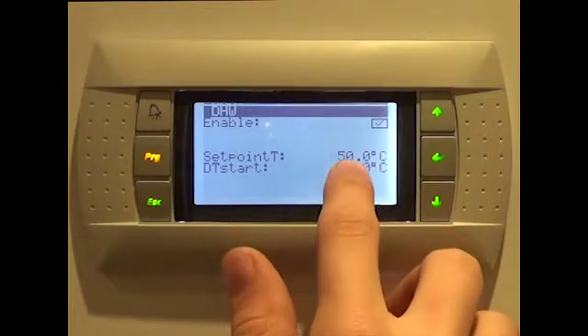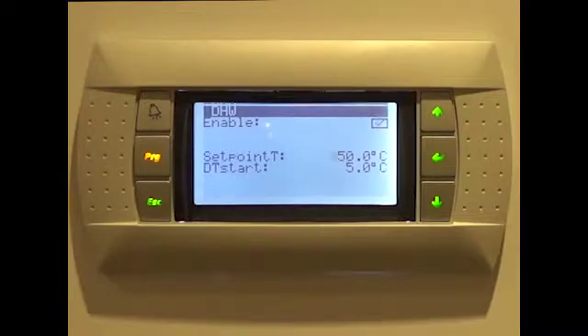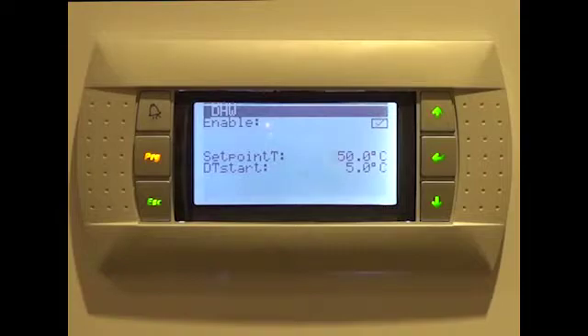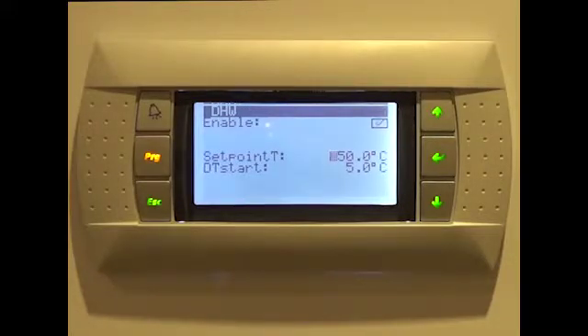The DT start temperature is the margin you will let the setpoint drop by. In our example, this is 5 degrees. This means that when the water drops below 45 degrees, it will kickstart the boiler back into action until the temperature has reached 50 degrees again, at which point it will switch off until the temperature drops below 45 degrees.